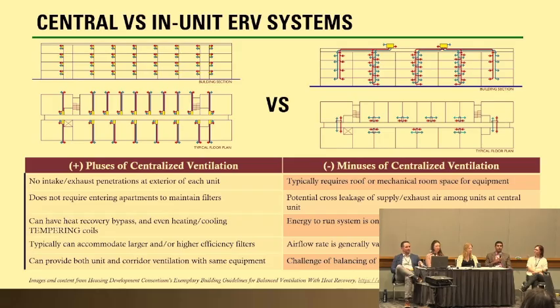For example, the ventilation system for the building uses energy recovery ventilators, which is basically a ventilation and exhaust system that also recovers energy in a box, to reduce heating and cooling energy use in the building. Great technology. Most states are starting to adopt this requirement in multifamily development, so it's becoming more common. But PHIUS has very high performance requirements on the system, and it also has this air tightness requirement, which a lot of these systems challenge. We have a diagram here. Most people might be familiar with ERVs that go in every apartment, with two ducts that go to the outside. Well, that's putting a bunch of holes in your building envelope that make it very challenging to meet that tight air leakage requirement.